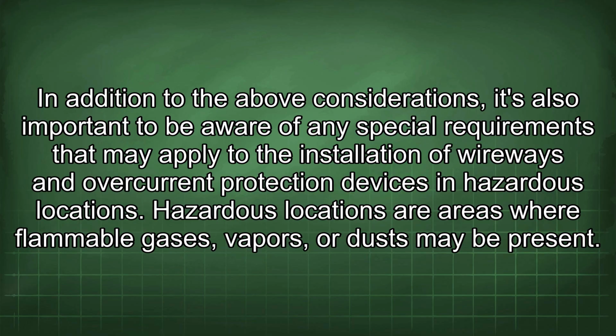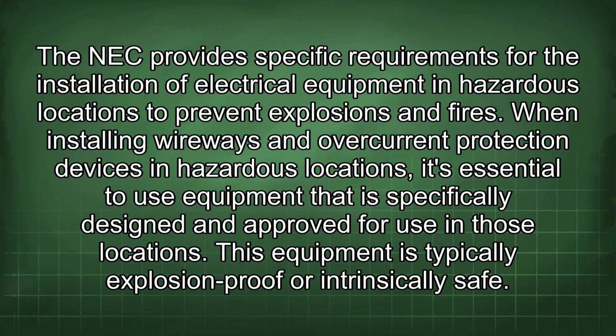In addition to the above considerations, it's also important to be aware of any special requirements that may apply to the installation of wireways and overcurrent protection devices in hazardous locations. Hazardous locations are areas where flammable gases, vapors, or dust may be present. The NEC provides specific requirements for the installation of electrical equipment in hazardous locations to prevent explosions and fires. When installing wireways and overcurrent protection devices in hazardous locations, it's essential to use equipment that is specifically designed and approved for use in those locations. This equipment is typically explosion-proof or intrinsically safe.